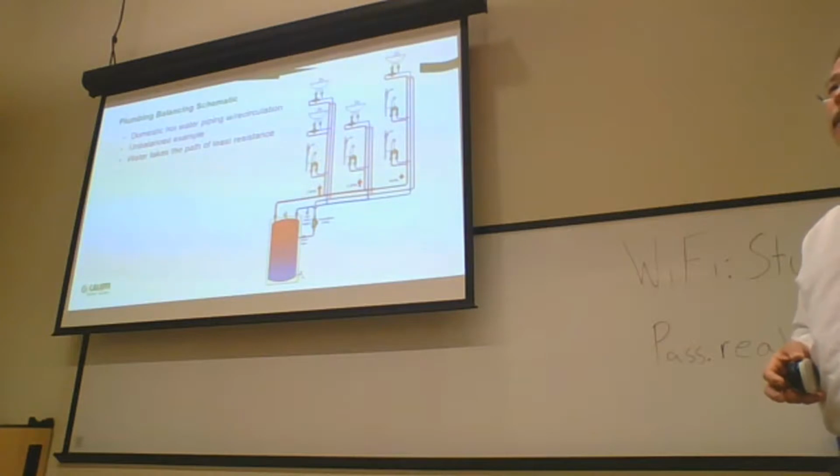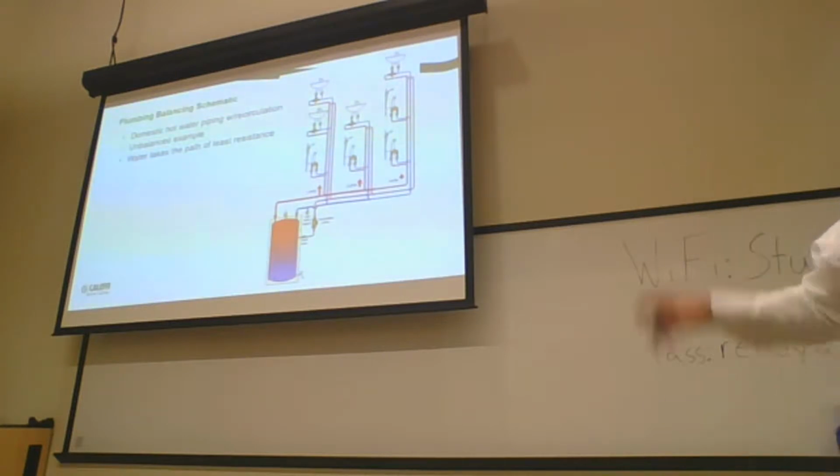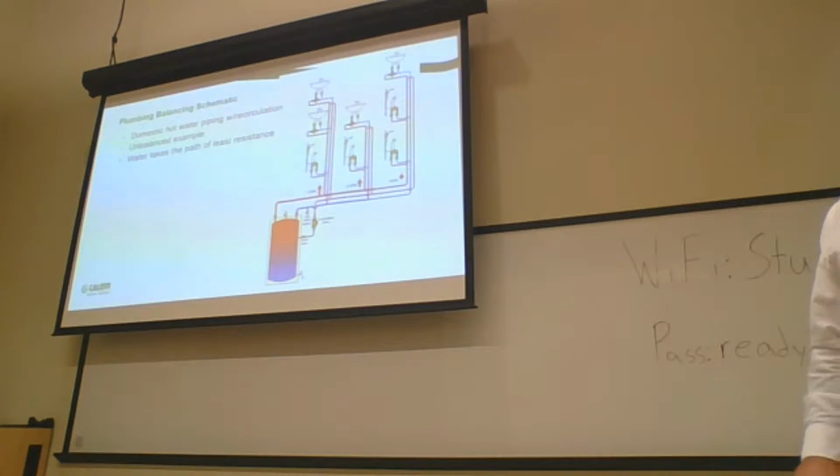The engineer might say, three circuits, just set them all the same, but you've got a 5 GPM pump and circuit setters that can't measure that divided by 3. Okay, so sizing, the valves are not always sized properly. What else? Too big of a pump? We hear a lot of solutions are to put in a bigger pump. If that guy on the far east end doesn't have any domestic hot water, upsize the pump. Is that the right answer?